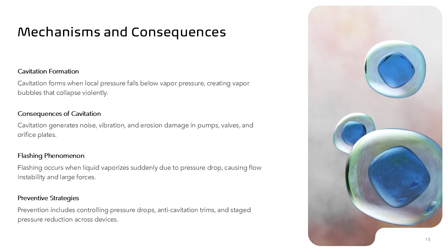Both mechanisms introduce transient excitation into the piping system, increasing fatigue risk and reducing equipment life. Preventive strategies include controlling pressure drops, using anti-cavitation valve trims, and staging pressure reductions across multiple devices. Addressing cavitation and flashing is critical for maintaining operational reliability and minimizing maintenance costs.